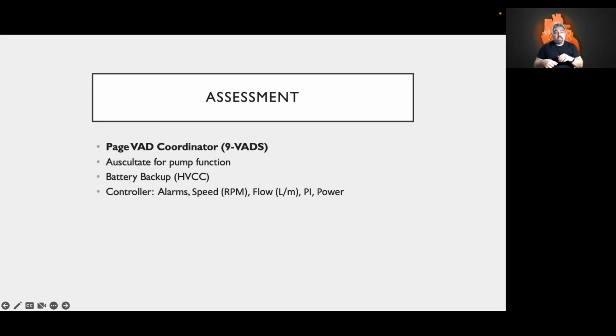And also worth noting that only speed and power are directly measured. Everything else is calculated. So the flow is based off of the RPMs. It's a calculation. So for example, if you have a thrombus and the pump is increasing the RPMs and drawing more power to try and compensate, it'll show a high flow, even though it physically has a reduced flow.